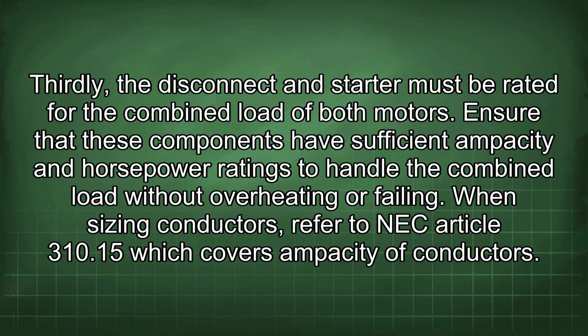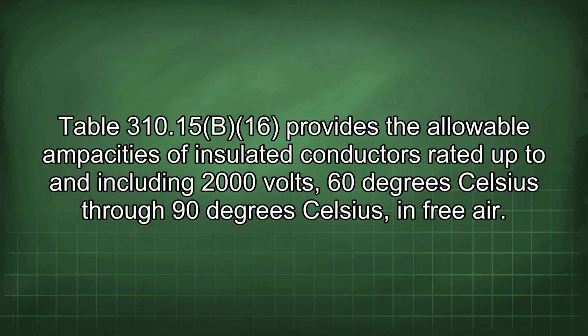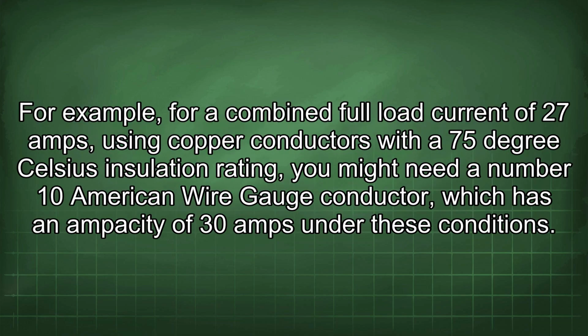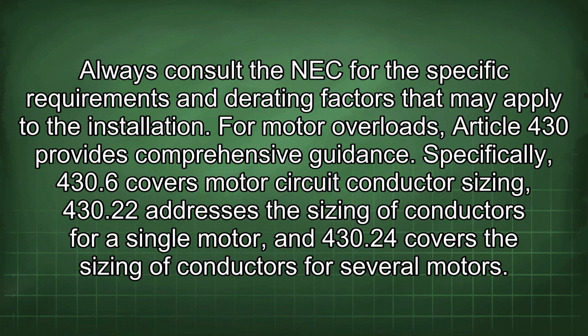When sizing conductors, refer to NEC Article 310.15 which covers ampacity of conductors. Table 310.15(B)(16) provides the allowable ampacities of insulated conductors rated up to and including 2000 volts, 60 degrees Celsius through 90 degrees Celsius in free air. For example, for a combined full load current of 27 amps, using copper conductors with a 75 degrees Celsius insulation rating, you might need a number 10 American wire gauge conductor, which has an ampacity of 30 amps under these conditions. Always consult the NEC for the specific requirements and derating factors that may apply to the installation.